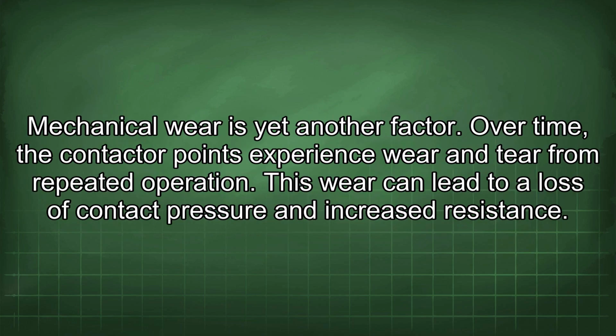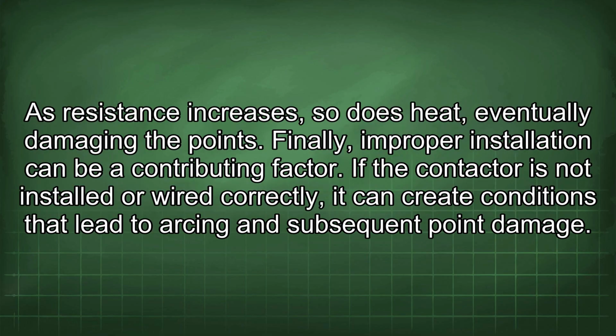Mechanical wear is yet another factor. Over time, the contactor points experience wear and tear from repeated operation. This wear can lead to a loss of contact pressure and increased resistance. As resistance increases, so does heat, eventually damaging the points. Finally, improper installation can be a contributing factor. If the contactor is not installed or wired correctly, it can create conditions that lead to arcing and subsequent point damage.